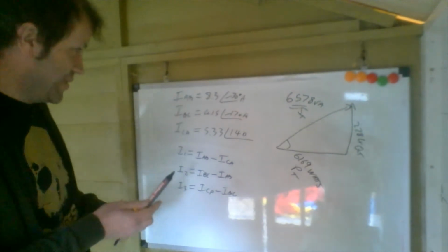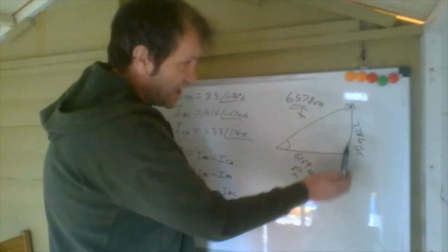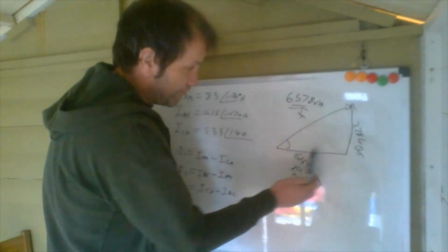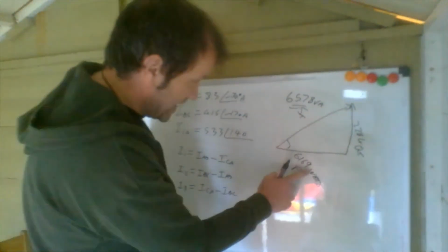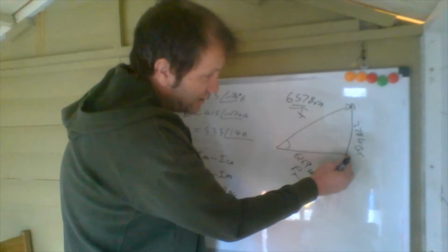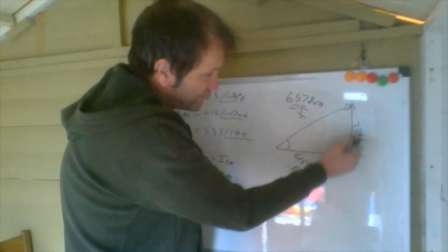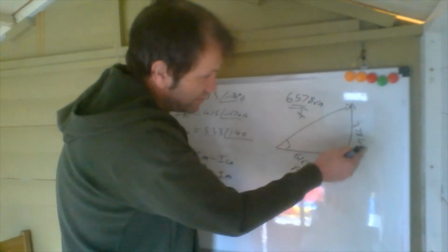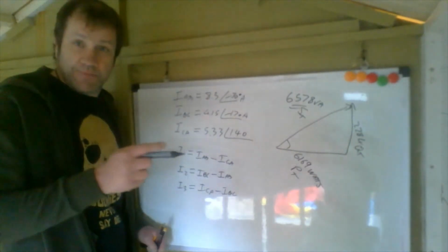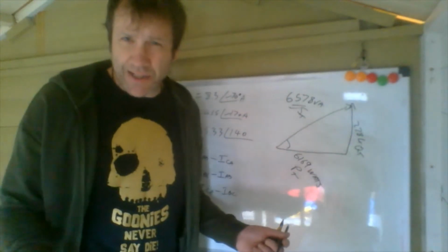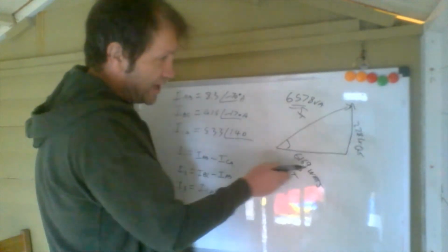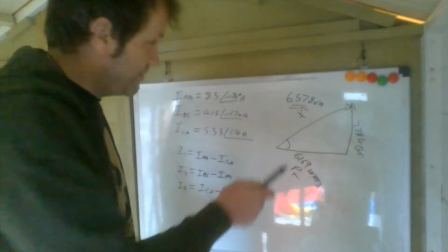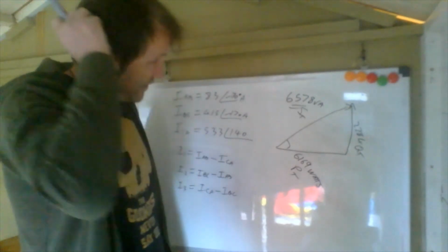Right, and when you add all these up, what we've got there, there's 6169, your power, and your reactive power 2284 up the side there. We just use Pythagoras again, and square that and square that, add them, get the square root. It gives you 6578. That's what I got.